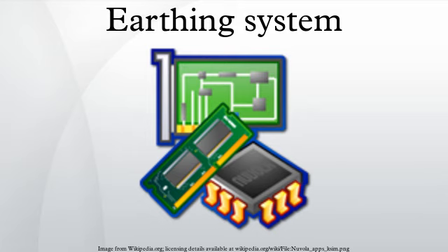Three-phase HV/MV power transformers, located in distribution substations, are the most common source of supply for distribution networks, and type of grounding of their neutral determines the earthing system. There are 5 types of neutral earthing: solid earth neutral, unearthed neutral, resistance earth neutral, low resistance earthing, high resistance earthing. Reactance earth neutral, using earthing transformers. Solid earth neutral.